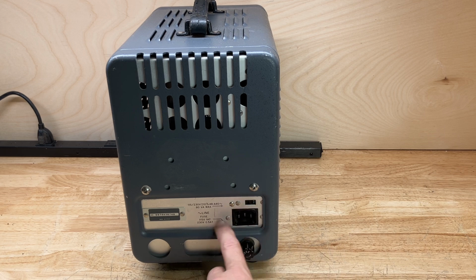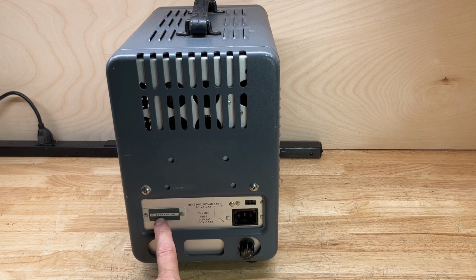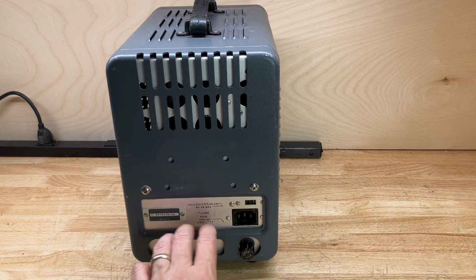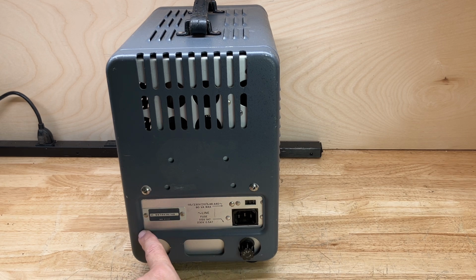This one has a new style receptacle on the back for the power cord. Most of them have a line cord directly, permanently attached to the back of the instrument, so this one must be rather new. If you look at the serial number prefix of 970 or 979A, that would indicate that this instrument was manufactured in 1969, or maybe a little bit after that even. So this is one of the later ones that HP made of the 400H.